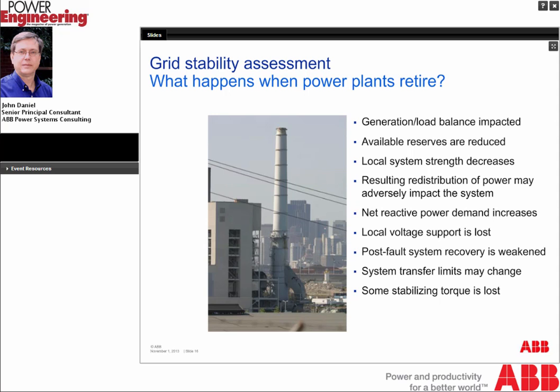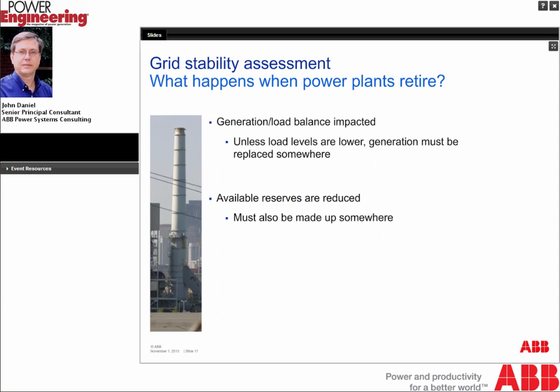Recently, a large utility in the U.S. was interested in retiring a large coal-fired power plant that was over 30 years old and provided some 500 megawatts of power. It also provided local voltage support and held up the local high voltage transmission grid. So it was very important for them to be able to study what would happen when it was retired. Well, there's a fairly large list of things that need to be considered when the plants retire because of changes to the network. To briefly touch on some of those, for instance, the generation load balance, of course, will be impacted. Unless you have a decreasing load level, generation will need to be replaced in some manner. The loss of the generation also potentially reduces the reserves that are available in the case of a contingency on the system, and those also will need to be made up somewhere.